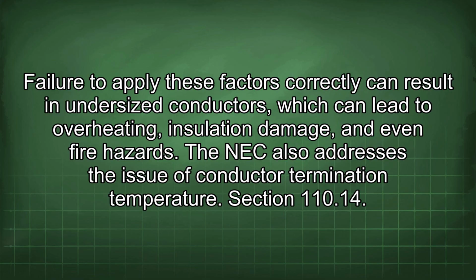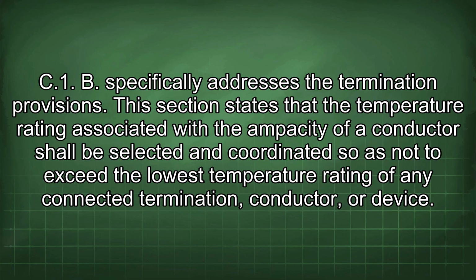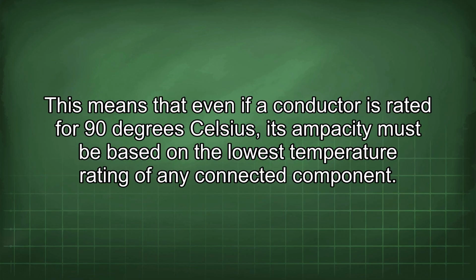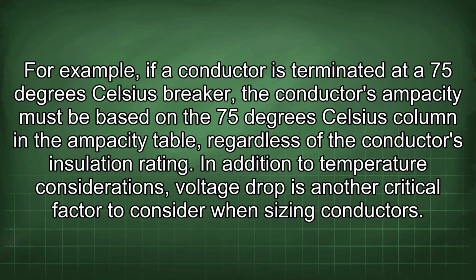Section 110.14(C)(1)(b) specifically addresses the termination provisions. This section states that the temperature rating associated with the ampacity of a conductor shall be selected and coordinated so as not to exceed the lowest temperature rating of any connected termination, conductor, or device. This means that even if a conductor is rated for 90 degrees Celsius, its ampacity must be based on the lowest temperature rating of any connected component. For example, if a conductor is terminated at a 75 degrees Celsius breaker, the conductor's ampacity must be based on the 75 degrees Celsius column in the ampacity table, regardless of the conductor's insulation rating.